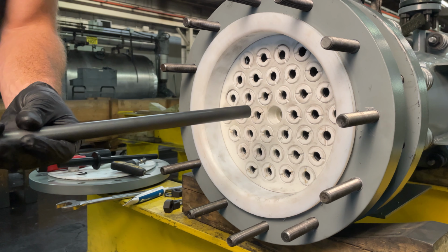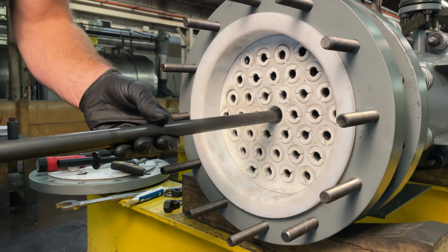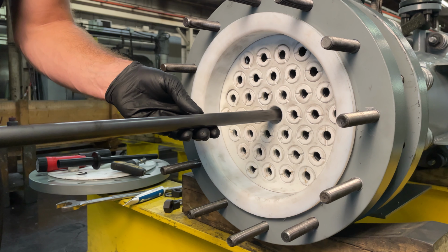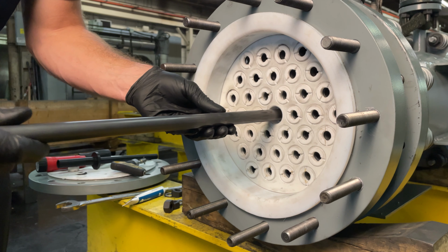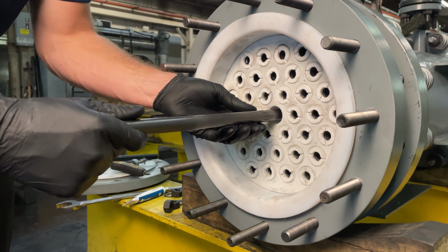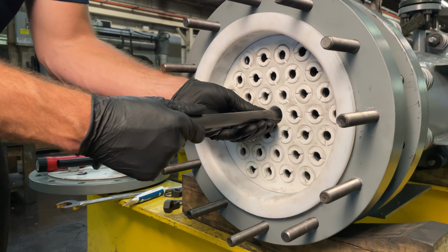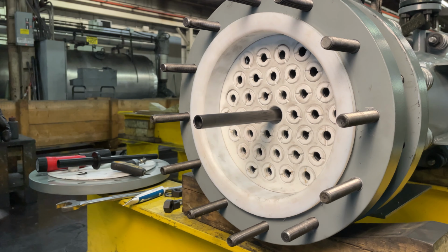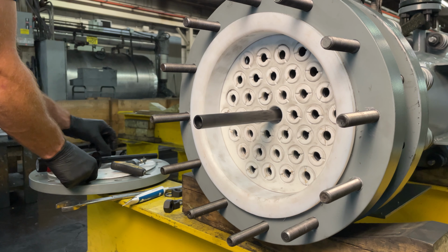Insert the tube slowly, being sure not to damage it as it moves through the baffle cage assembly. Once the tube is inserted, ensure that no damage was done to the leading edge. If a tube is chipped or damaged, it should be replaced. Leave enough working space on the tube to be able to apply the O-rings and backup rings.